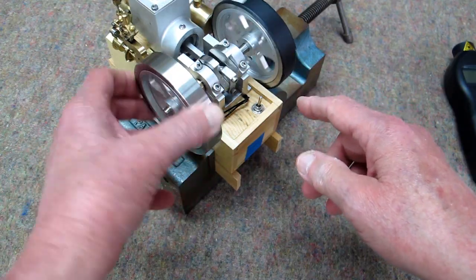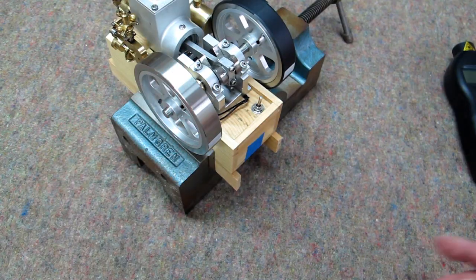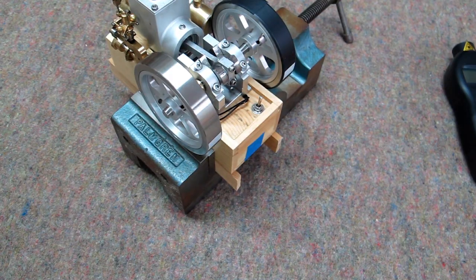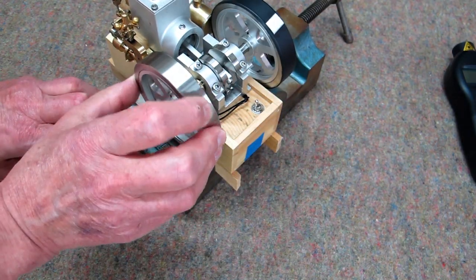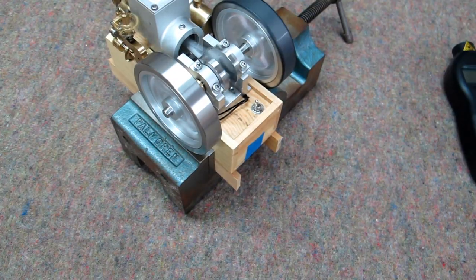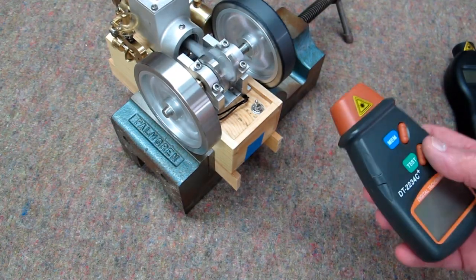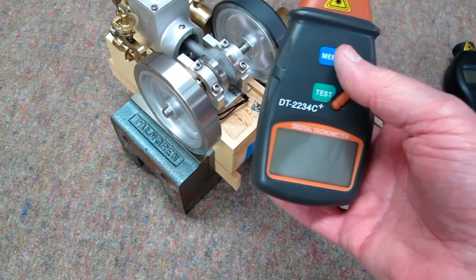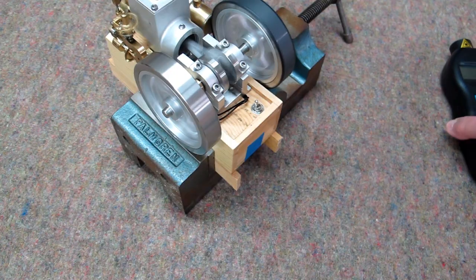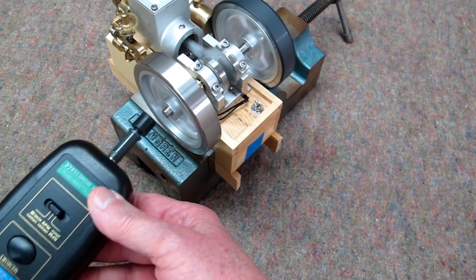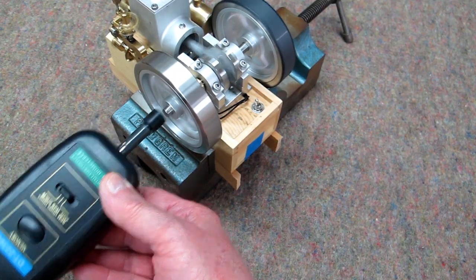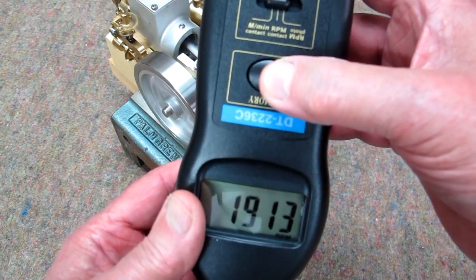More accurate. I've placed a second piece of reflective tape 180 degrees opposite and we'll try each tachometer. We should get twice the actual speed. We need to divide the reading by two. So it's just over 2,000 RPM. Using the contact, we're actually running about 1,900 right now.